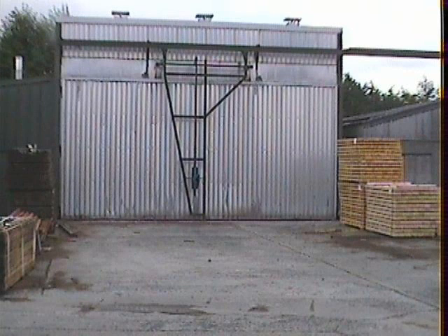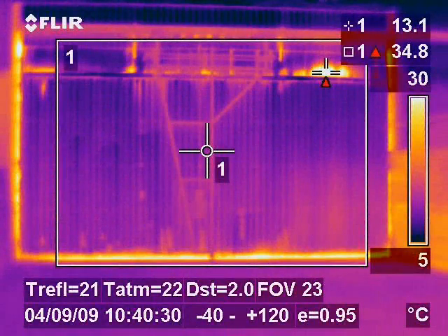This image shows a wood drying kiln, and the purpose of the inspection was to find where heat and energy was being wasted, and it's clear to see that poor door seals were letting a lot of heat escape around the door. This was a similar type project for a meat factory where we looked for energy savings. We found a lot of poorly performing door seals.